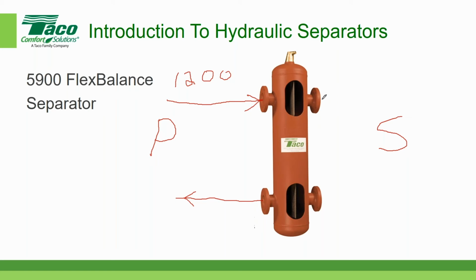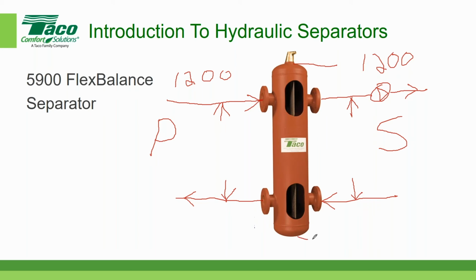So on the secondary side, let's assume that in this case, I'm going to show a secondary pump. And in the secondary side, we'll say that the flow is 1,200 gallons per minute. So that means that the flow across the hydraulic separator is going to be equal to 0. Now, because this is a pre-engineered device, there's a whole bunch of dimensions here that are taken into consideration when the engineers design this in for factory manufacturing. What's important are things like the distance between the connections, both on the primary side and the secondary side. The other thing that's important is the overall height of the hydraulic separator, and the distance between the top and bottom relative to the connections. The other important thing is the diameter over here.